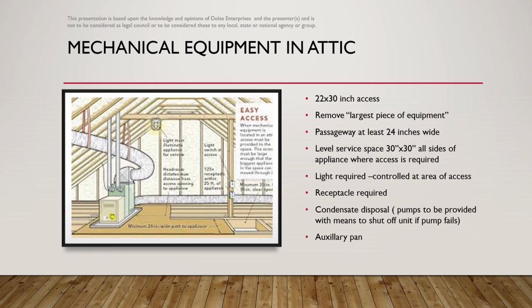For mechanical equipment located in attics of single-family residential dwellings, the code provides for the following. At a minimum, a 22 by 30 inch access door is required to gain access to the attic area. Remember, the code also has language in there that says or removal of the largest piece of equipment. A passageway must be developed to the equipment. The passageway shall be at least 24 inches wide. There shall be a level surface space 30 by 30 on all sides of the appliance where access is required.